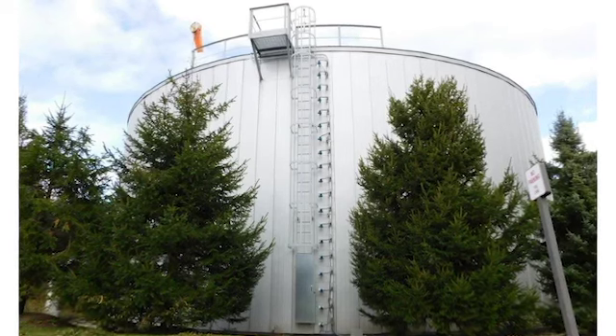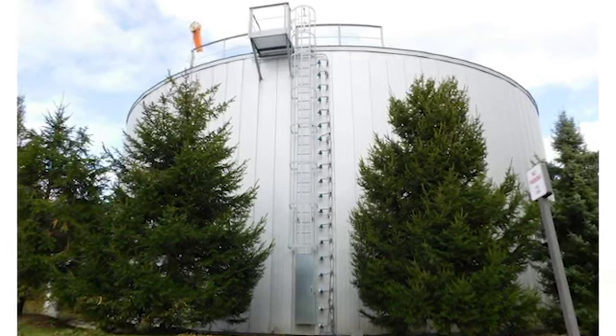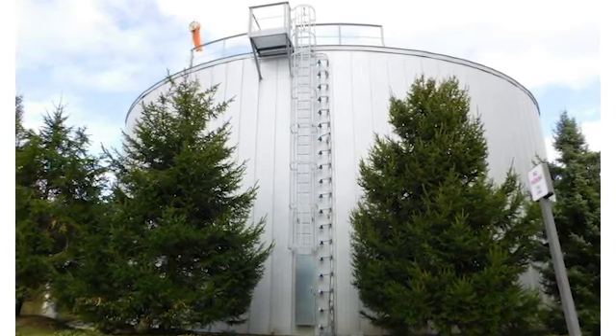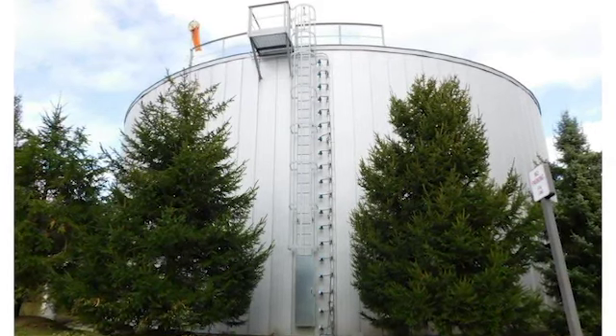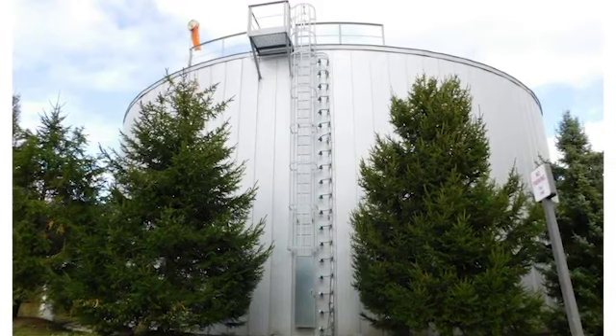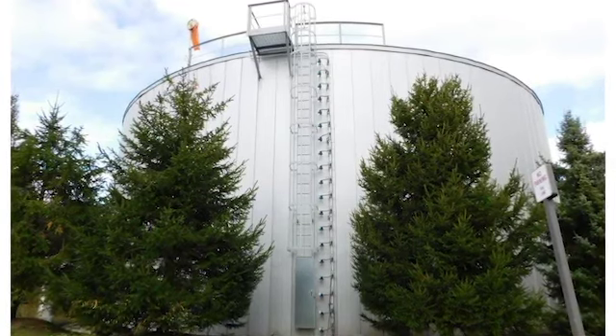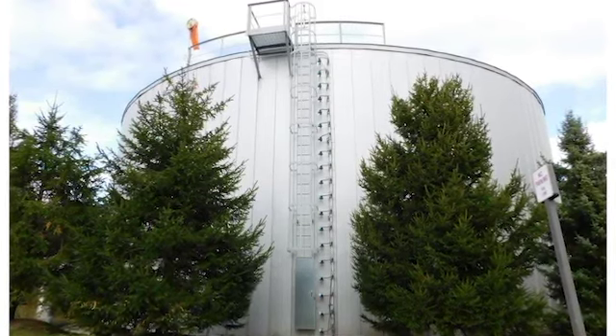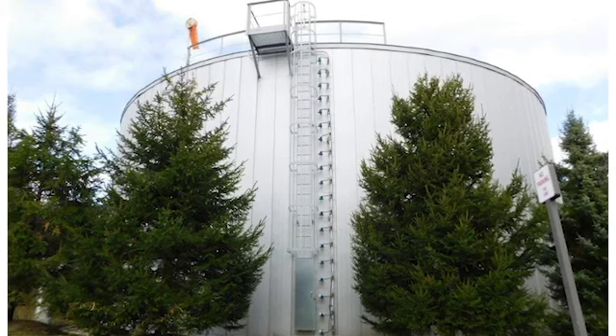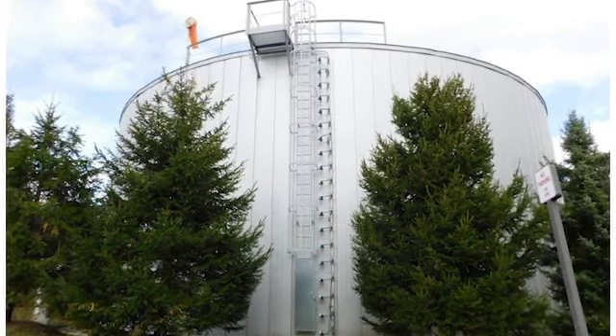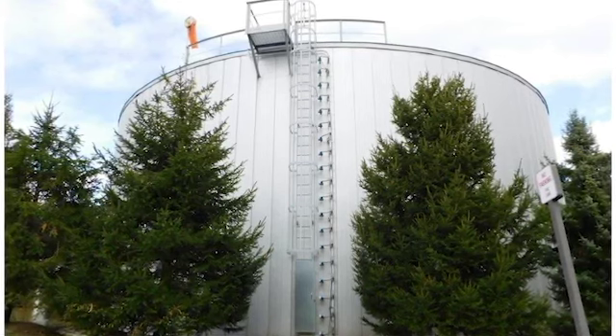Okay, so when the market conditions are at a point where it's time to dispatch, this tank is just like putting on a battery. It allows us to shut down the chiller and provide that chilled water to the hospital, and it's totally seamless to them. They have no idea that we're in a dispatch mode.